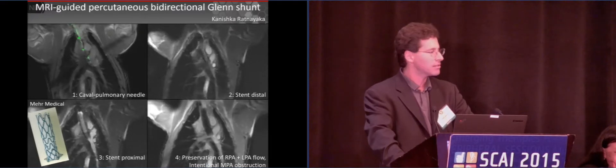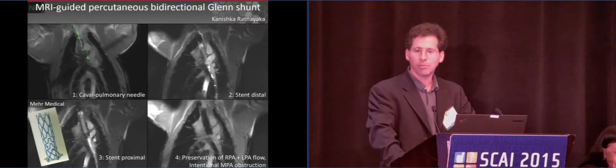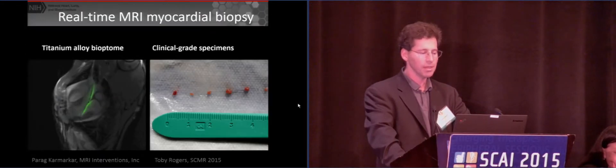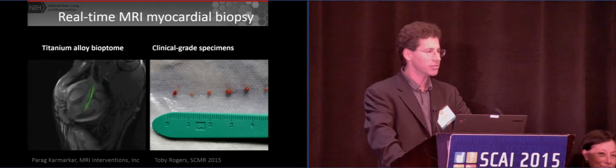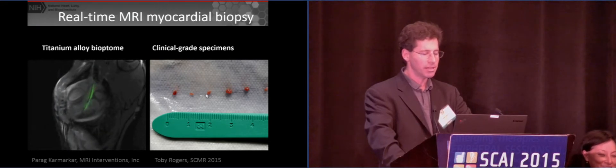It's not magic — it's that we have a great imaging tool, and if you were equipped with better imaging tools, you could do a better job in your daily life. Here's a project we've been working on for about eight years, mostly failure. The $15 disposable stainless steel bioptome you buy in the store is great, but if you replace it with a metal that's not going to destroy an MRI image, it's very hard to get a cutter that's sharp. Finally we found a cutter that's nice and sharp, and it's cute that we can steer our bioptome, see the tissue, and get realistic specimens. That's just a prototype — stay tuned.